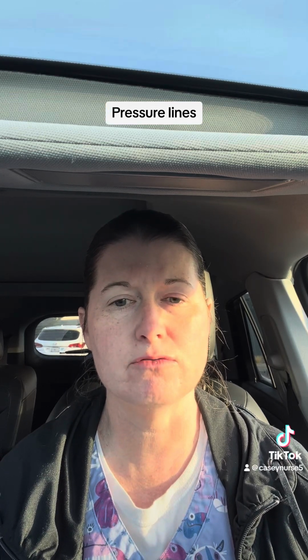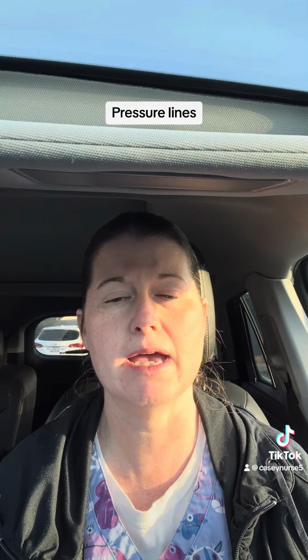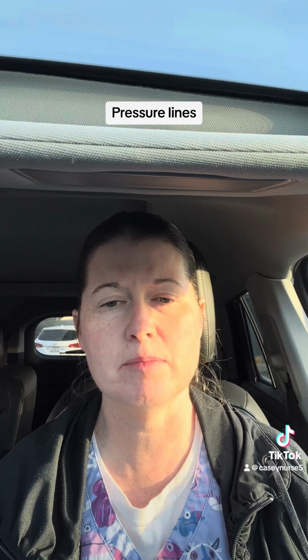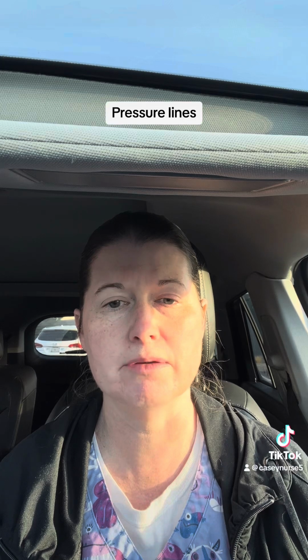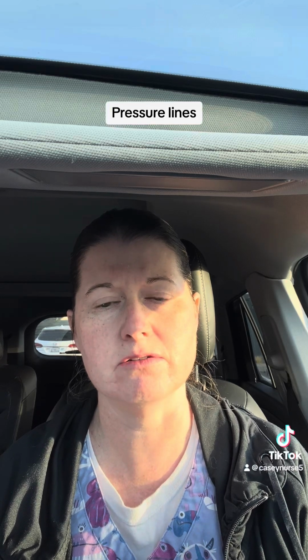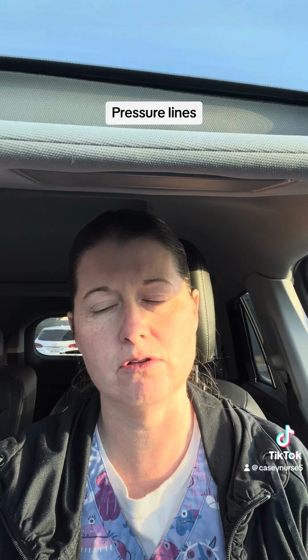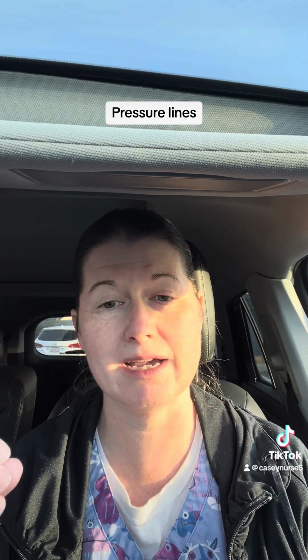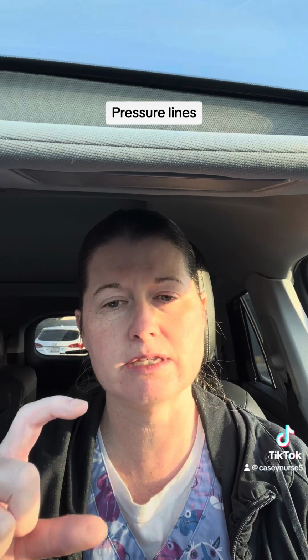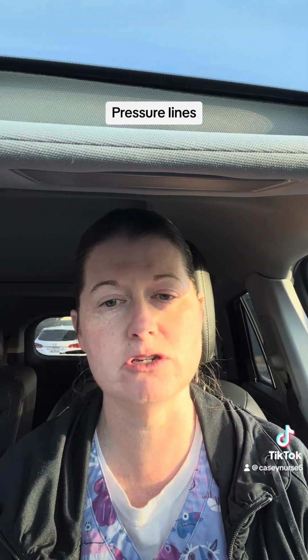They all have a bag of normal saline, usually a 500 ml bag, and it's in a pressure bag pumped up to 300 millimeters of mercury. That allows for about 3 mLs an hour of fluid to be infused into the vessel. And then from the pressure bag, follow it along, you have squishy tubing like IV tubing. It has some give. And then you have a transducer, which is a rectangular little plastic box. And that's what turns our pressures into a waveform that we can actually measure on the monitor.